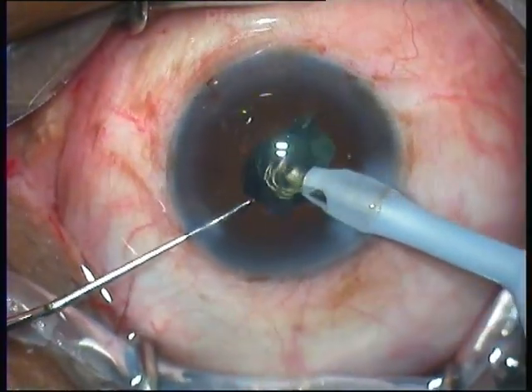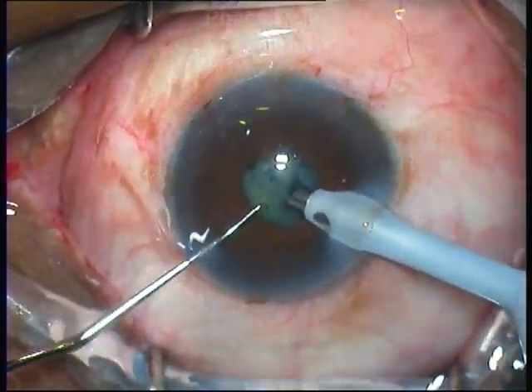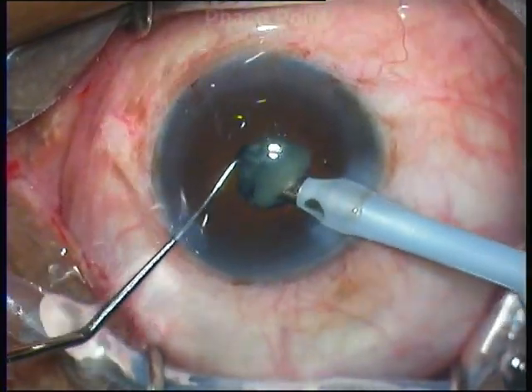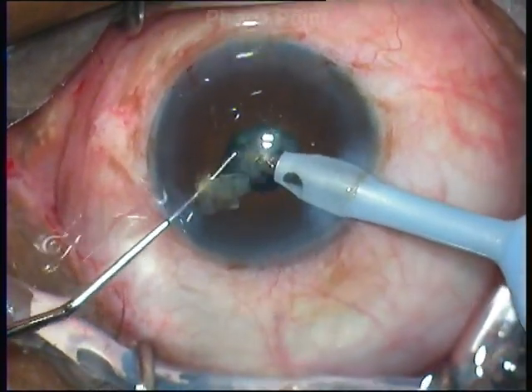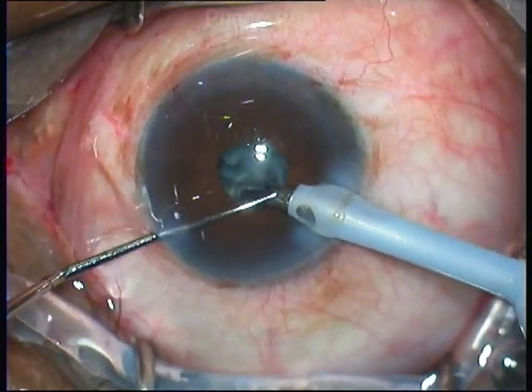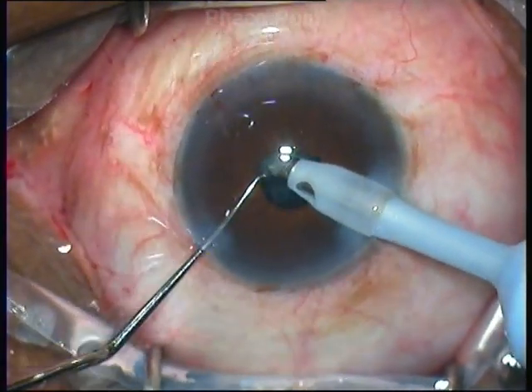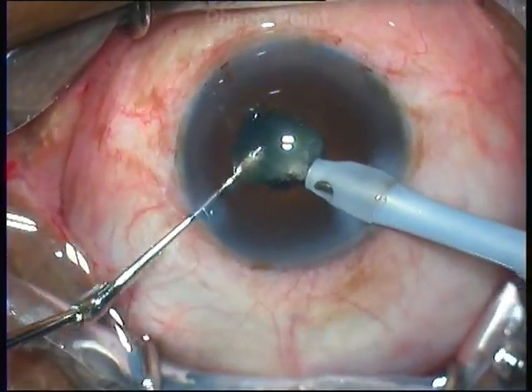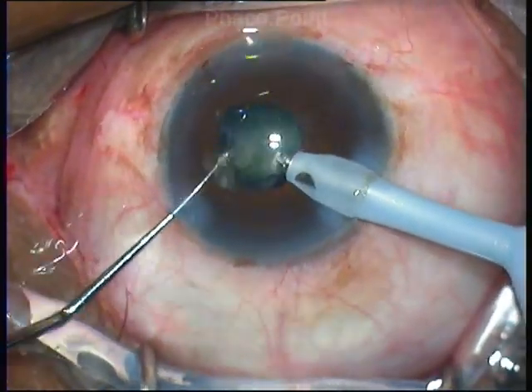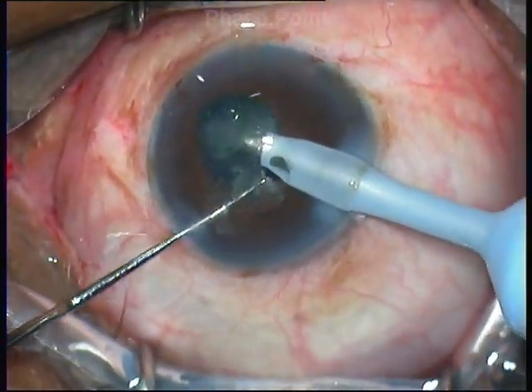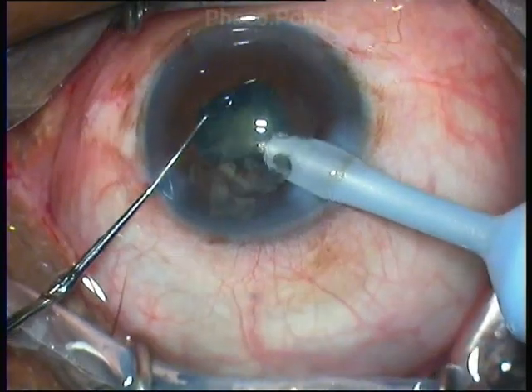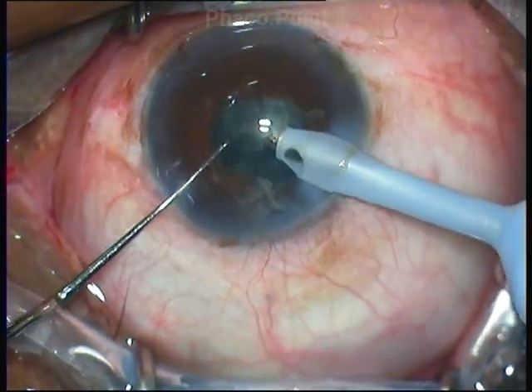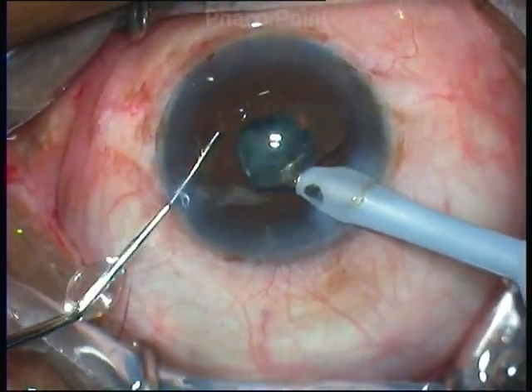And there is good fragmentability of the pieces, and in spite of this, you find that there is no tendency of the pupil to be dragged into the phaco tip. This major advantage of the peristaltic machine occurs because the vacuum buildup will occur only after occlusion of the tip is obtained. Let's switch over and see what happens in the Venturi machine.